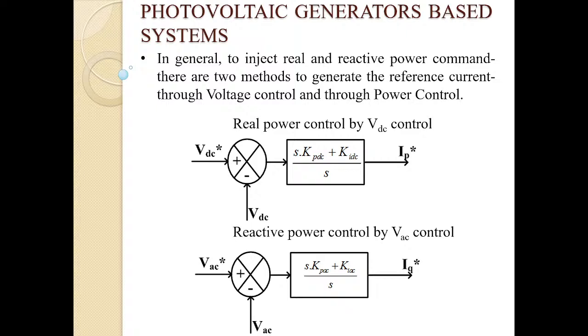On the other hand, AC voltage control can be required for reactive power. However, in grid connected mode of operation, normally we don't go for a PI controller, but we go for droop control in the AC voltage. The DC voltage control is normally followed by a PI, but in the AC voltage controller, we many times just put a droop in place of the PI controller. So VAC reference minus VAC, with a proportional control, not a PI control, produces the IQref. That way, the IPref and IQref are generated for controlling the smart inverter.